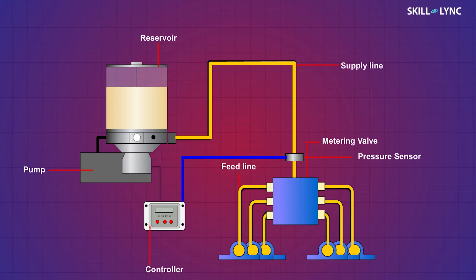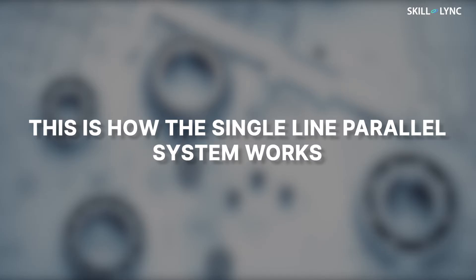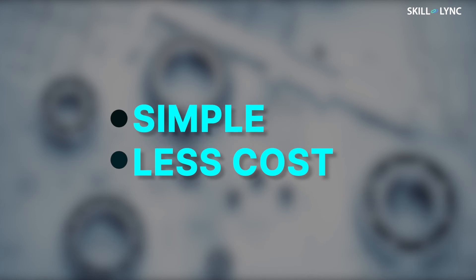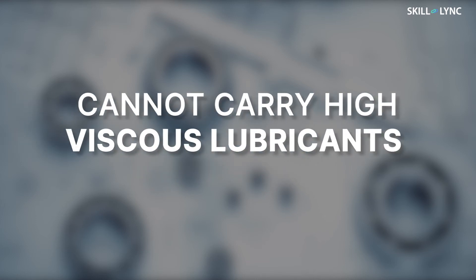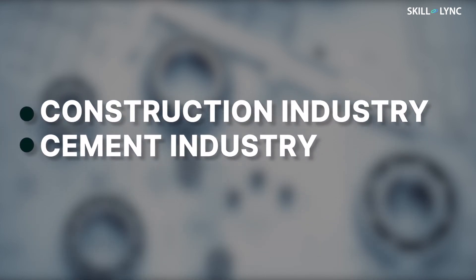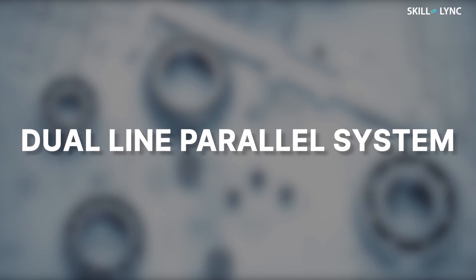The pressure in the lines will then get relieved. This is how the single line parallel system works. This system is simple and less costly, but it cannot carry high-viscous lubricants. This system is used in machineries in the construction and cement industries. The next type is the dual line parallel system.